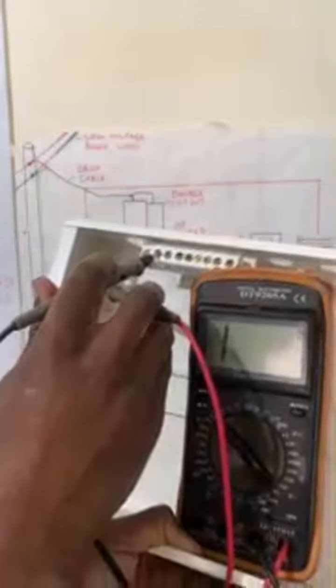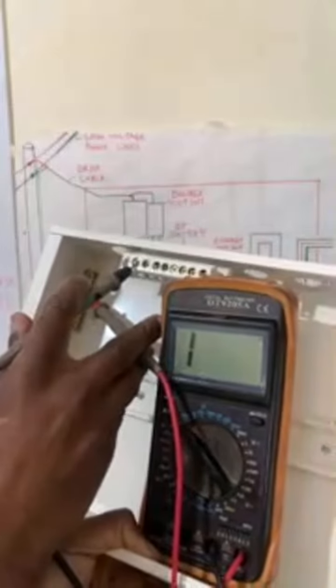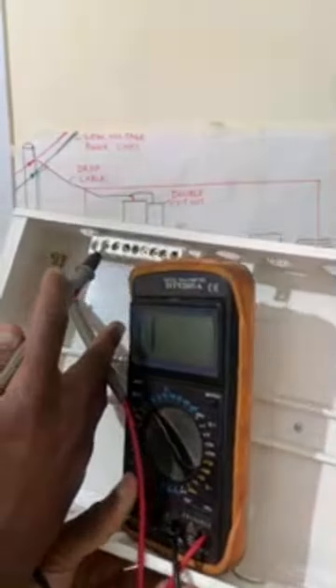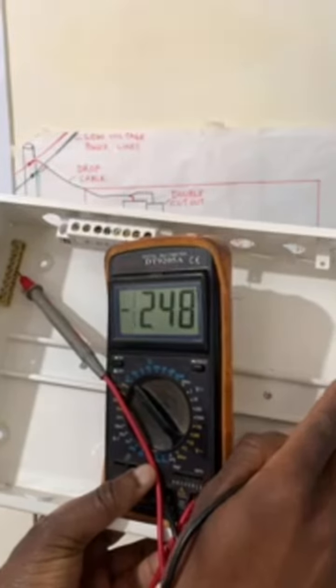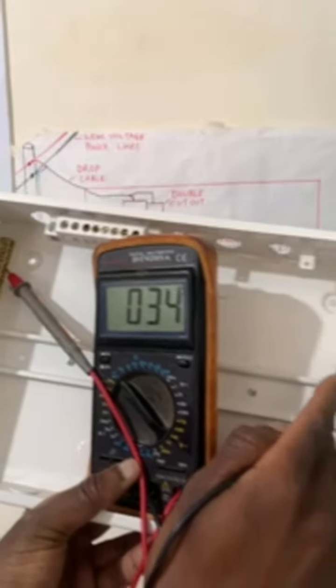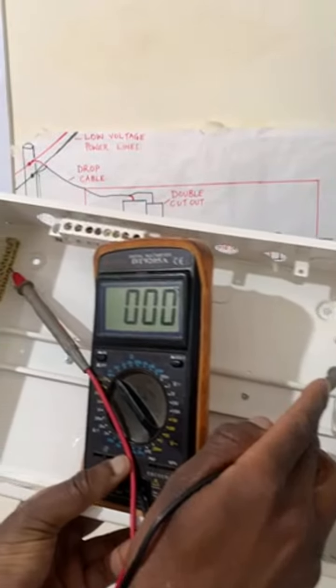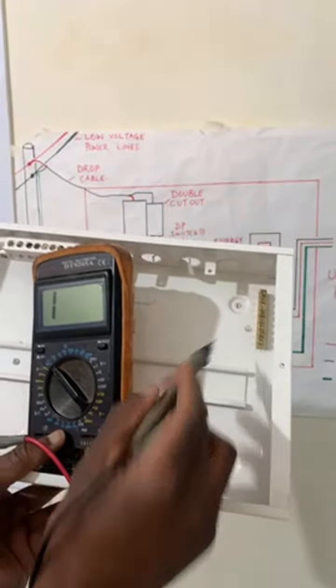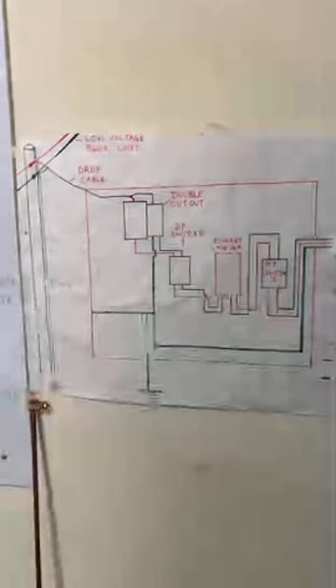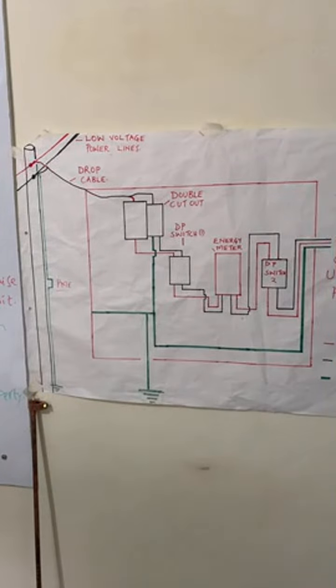So we start by placing a probe at one of the earth bars, and on the neutral bar we have one, meaning that indeed they are not in contact. Infinity, when we place there. On the other earth bar, they are in contact with each other, meaning that they are circuiting. So that directly tells us that indeed that is a perfect connection for the earthing. But again, to strengthen it, you must link the two earth bars.